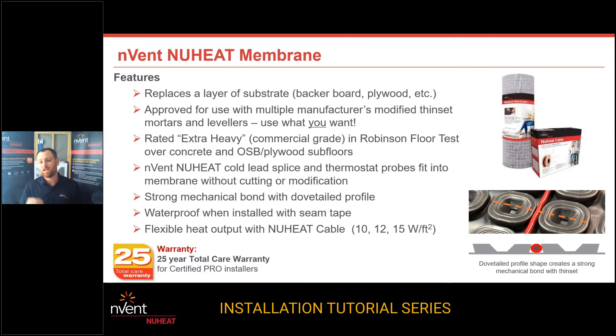When it comes to membrane, we have different heat outputs. You are in control of your cable spacing, meaning that your wattage output — you're now in control. You have the ability to do 10 watts a square foot, 12 watts a square foot, or 15 watts a square foot. All of those are going to be different spacings in the membrane, and they're all going to use up a different amount of square footage. Those are the benefits of using a NuHeat Cable system with a NuHeat Membrane system.